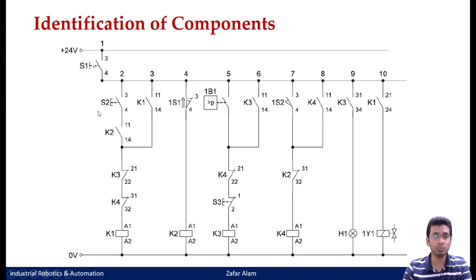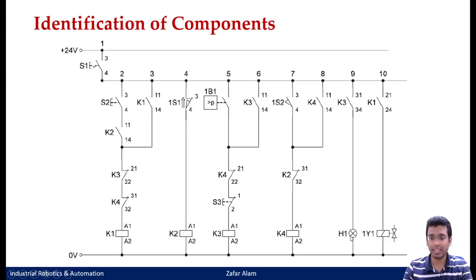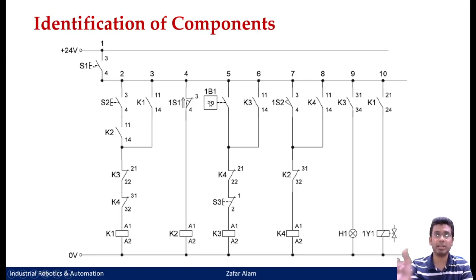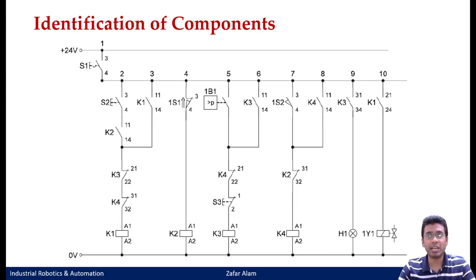Then I have my limit switch — 1S1. I have another limit switch, a normally open type: 1S2. I can identify some relays: K1, K2, K3, K4. I can also identify my lamps denoted by H — H1 means this is only the first lamp. Similarly, I can identify my solenoid valves denoted by 1Y1. I can also identify some pressure sensors denoted by 1B1 — this pressure sensor is associated with one of my pneumatic cylinders. So these are the different types of components in this circuit.